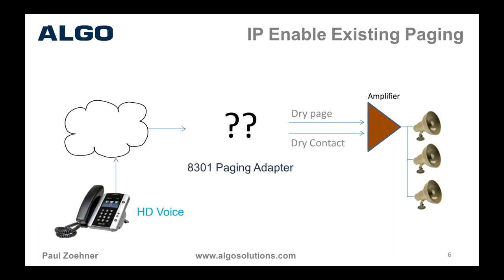So this is where the Algo 8301 was really intended for. This is the application it was specifically designed for. On the left side, we have a PoE IP interface, whether that be SIP or multicast, to the network. So very friendly from the network side, is administered through a web interface. And on the right side, we emulate the dry page port that you would have had from this old style phone system. And you get a lot of features with this device, which I'll begin explaining in a few moments.